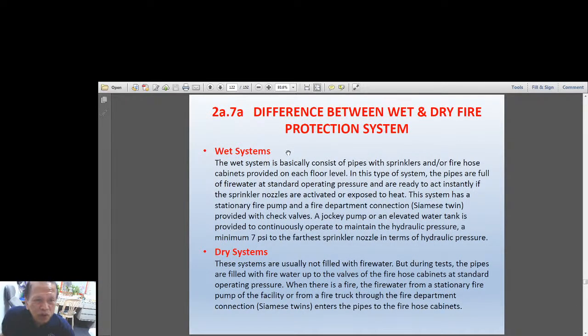Okay? So we have two systems in water protection or fire suppression using water. You have the wet system and the dry system. You say wet system when there is water inside the pipes with the jockey pump running every now and then to maintain the pressure. While in a dry system there is no water inside the pipe, so water will only come in when a fire pump runs, okay, when it operates. So like a dry standpipe, the dry standpipe of a building, there is no water there. While the wet standpipe has water already, ready to come out and be sprayed to the fire.